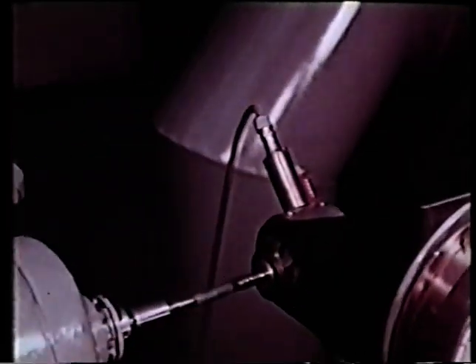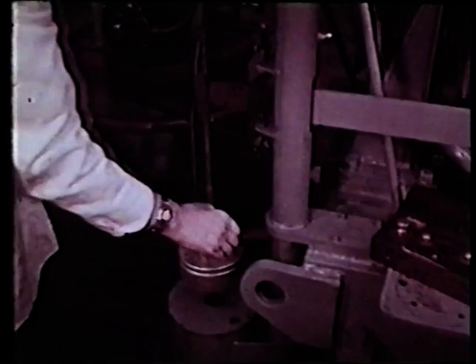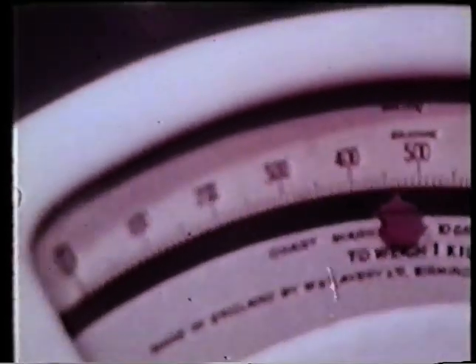The precision with which the components of power may be measured using electronic speed measuring devices and dynamometer torque meters of high absolute accuracy, combined with easily calibrated water measurement, enabled the efficiency to be demonstrated to the consulting engineers with far greater accuracy than on full-scale tests.